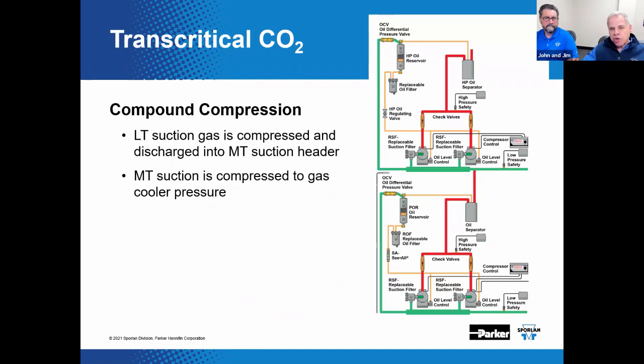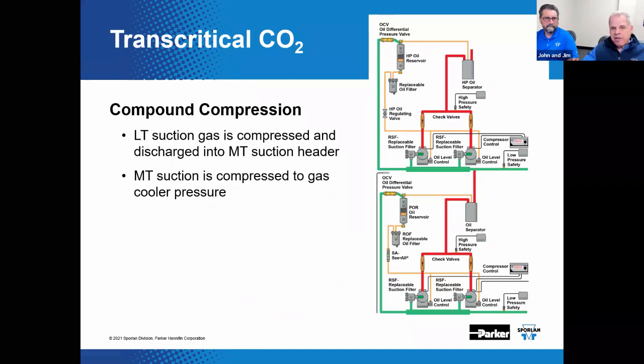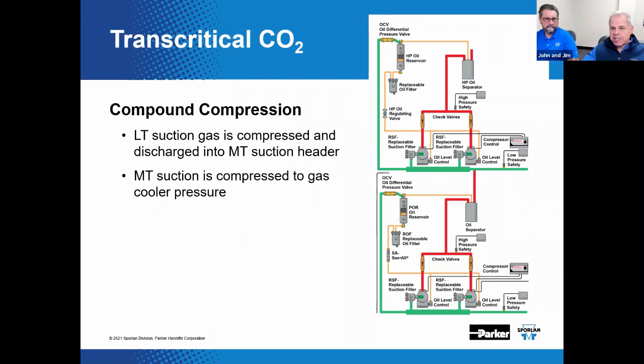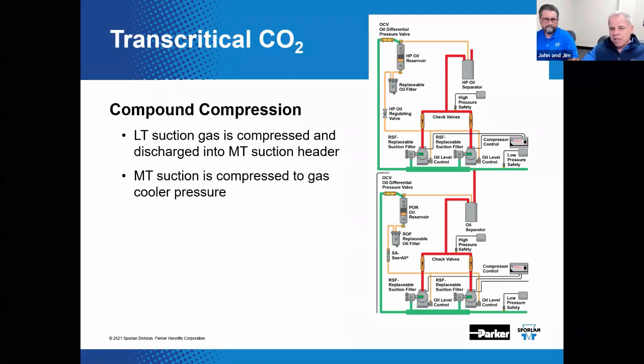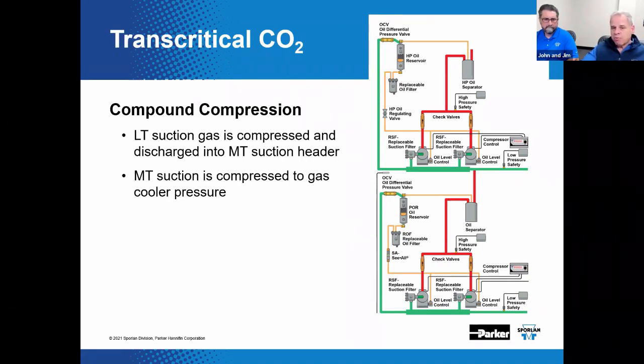This section shows compound compression. Instead of having a heat exchanger, like in the case of cascade CO2 with DX, this version directly feeds the low temperature discharge into the suction of medium temperature compressors. So you've got a bank of compressors here and a bank of compressors up there. Now, keep in mind, only CO2 is being circulated throughout the system. This helps reduce the temperature difference and associated losses found in heat exchangers, like when we talked about that other method of doing things where the heat exchanger killed us. This helps transcritical CO2 systems improve overall system efficiency.